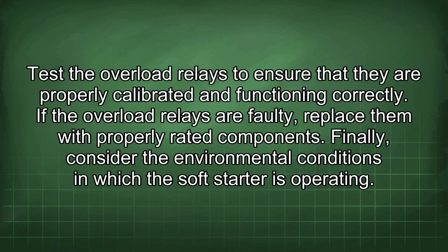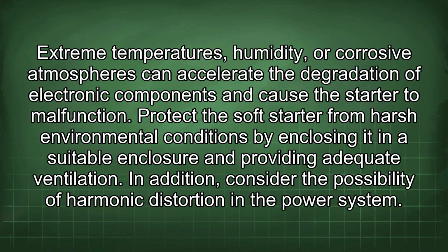Finally, consider the environmental conditions in which the soft starter is operating. Extreme temperatures, humidity, or corrosive atmospheres can accelerate the degradation of electronic components and cause the starter to malfunction. Protect the soft starter from harsh environmental conditions by enclosing it in a suitable enclosure and providing adequate ventilation.